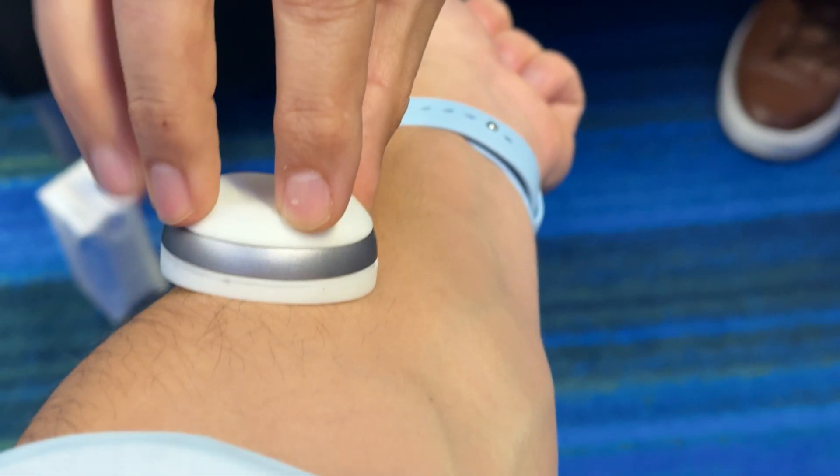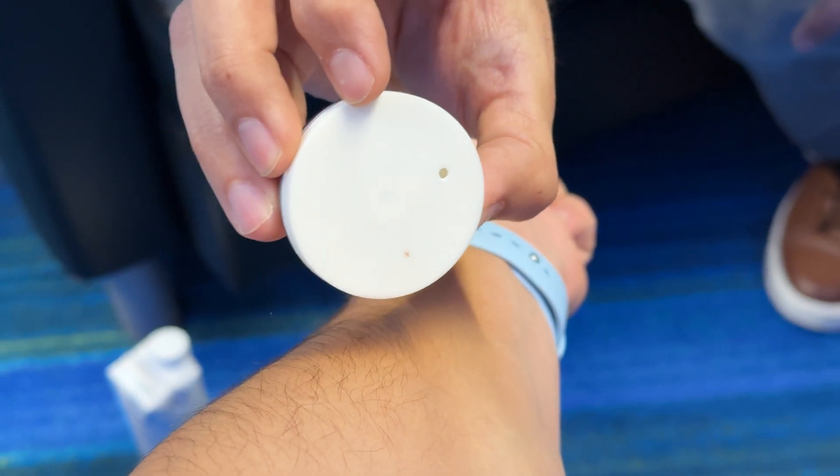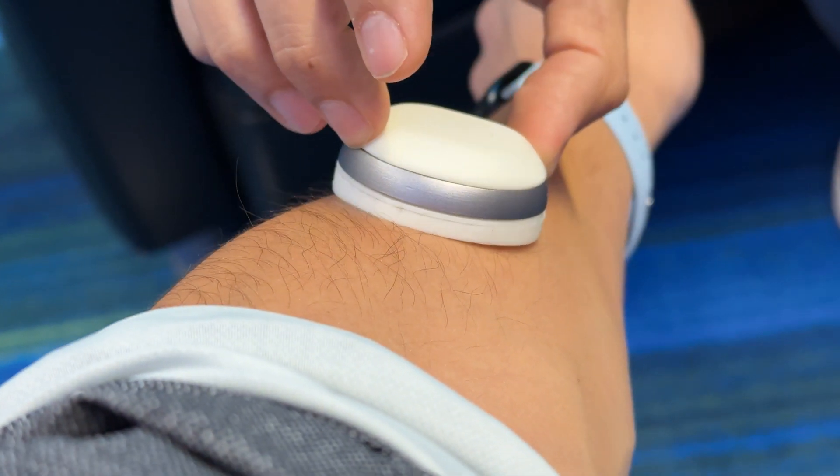The cartridge itself is disposable for seven days. So the bottom part — is that what injects a cannula, or is there a separate applicator? No. How does someone put this on? The mechanism we use is technology that automatically inserts by pressing the button in your application. The spring-loaded needle is released, the needle goes and injects into your body. So similar to what people experience with an Omnipod — they put it on, use an application, and it inserts. Exactly.